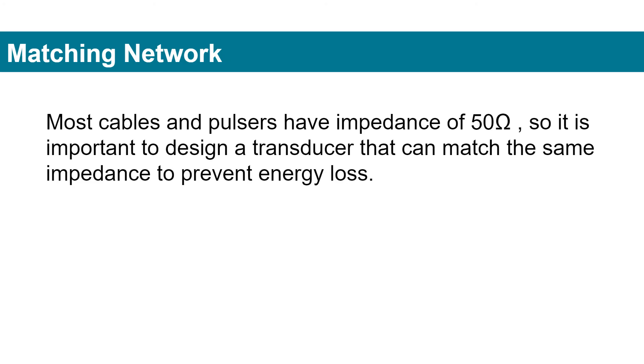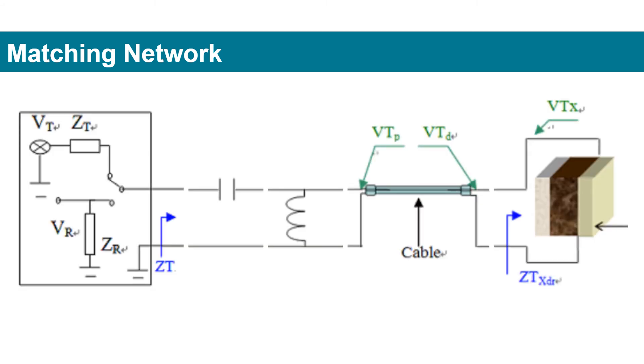Since most cables and pulsers have an impedance of 50 Ohm, it is important to design a transducer that can match the same impedance to prevent energy loss. For a small area transducer, an active material with a high dielectric constant is preferred. When a transducer's electrical properties differ from that of the circuit and cable, a matching network is needed to prevent reflections at each boundary. Most matching networks consist of inductors and capacitors, either in series or shunt connection.